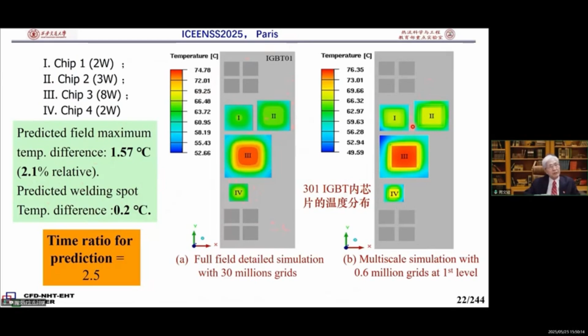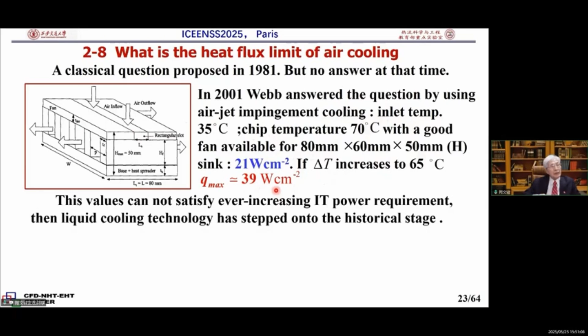Now, what is the heat flux limit of air cooling? This is a typical problem put forth in 1981, but at that time no answer was given. In 2001, we gave the answer. For the impingement situation, with inlet temperature 35, chip temperature 70, and a good fan available at that time, for a heat sink of 80 by 60 by 50, we got a heat flux of 21 watts per square centimeter. If the temperature difference increases to 65, then we may achieve a heat flux of 39 watts per square centimeter. Of course, this cannot satisfy the requirement for ever-increasing power, so liquid cooling technology has stepped onto the historical stage.